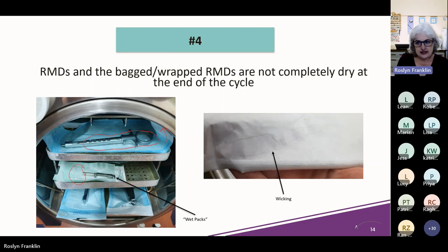Now these wet packs, they're subject to wicking. This means that microbes can enter through that wet packaging and recontaminate the instruments. You also might find these wet packs will lead to some instrument corrosion.